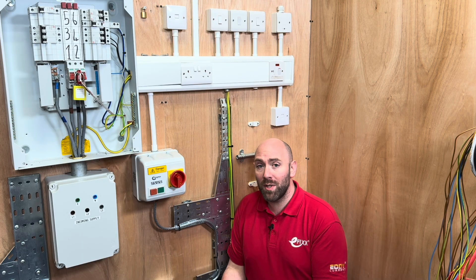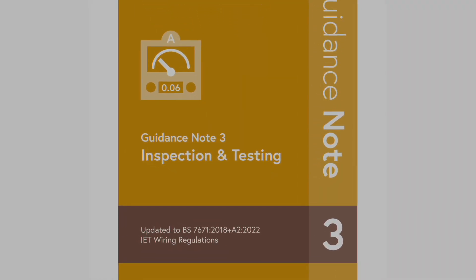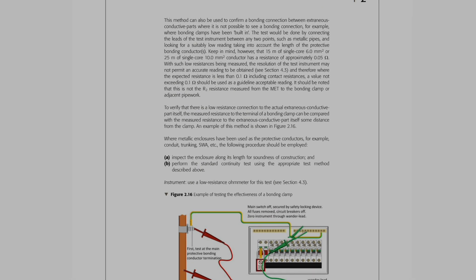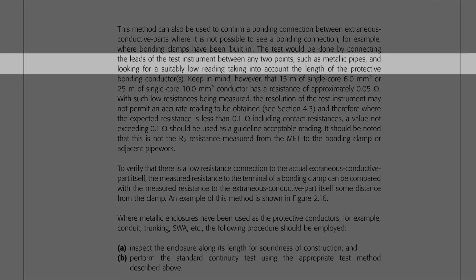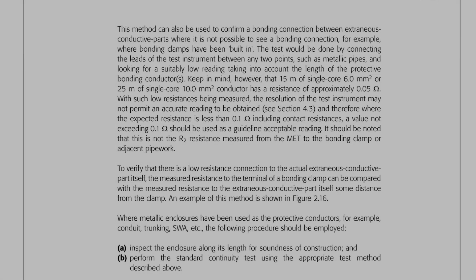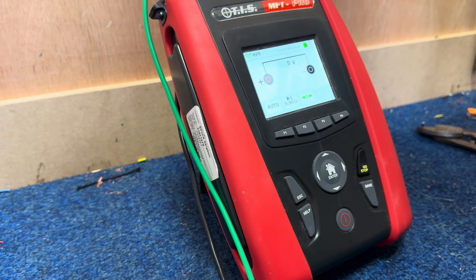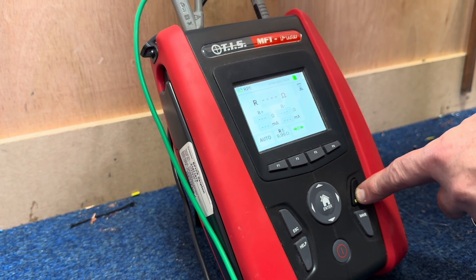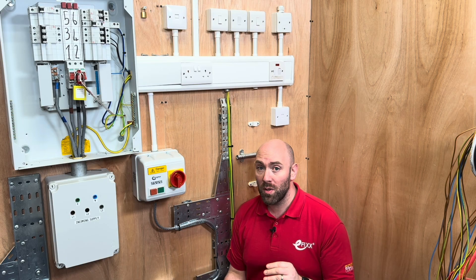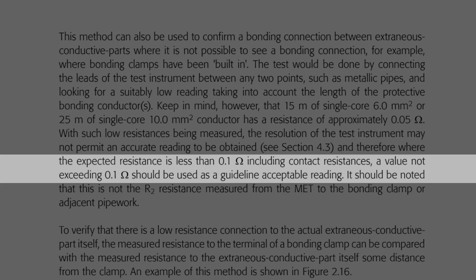You may be aware that the maximum permitted resistance for a bonding conductor is 0.05 ohms, but where does it say this? Truth is: nowhere. Guidance Note 3 does shed some light on this. The first paragraph of page 61 says the resistance between two metal pipeworks needs to be a suitably low reading, taking into account the length of the bonding conductor. It continues by highlighting that 15 metres of single core 6 millimetre squared cable and 25 metres of single core 10 millimetre squared cable is approximately 0.05 ohms. However, because the resistances are so low, test instruments — even top quality testers — are not able to accurately read to this low range. It is generally agreed that a reading less than 0.1 ohms is acceptable for bonding conductors.